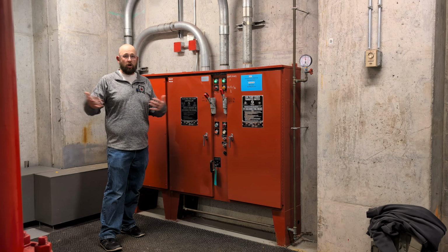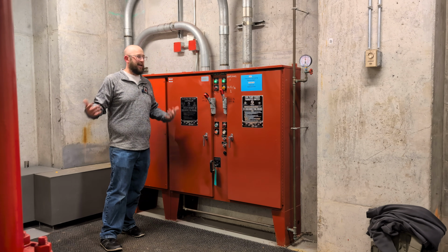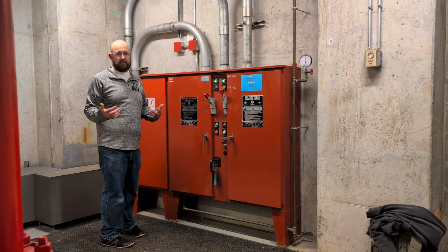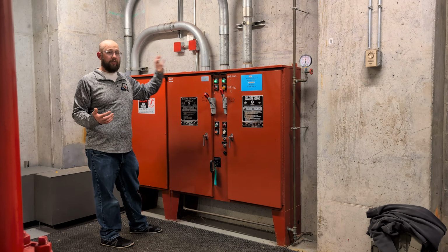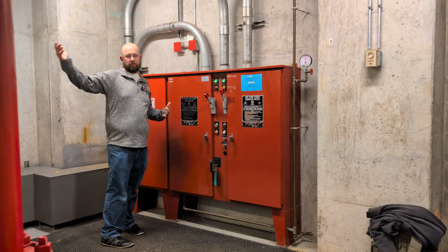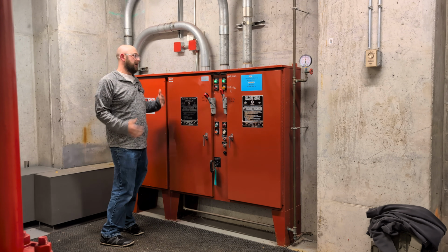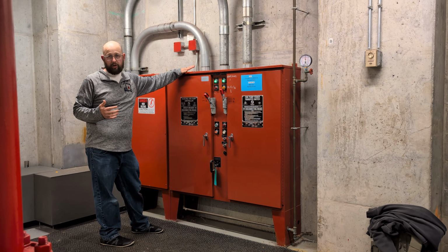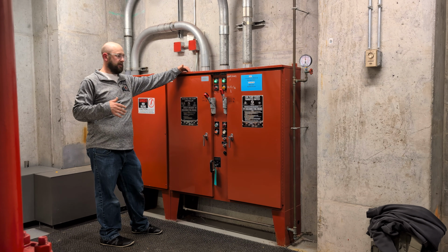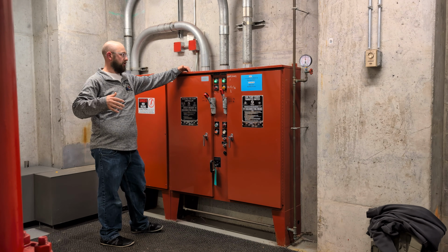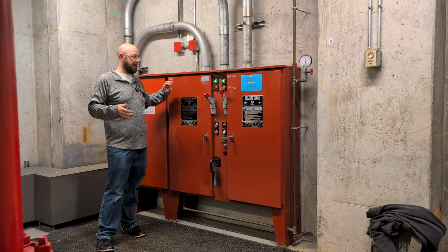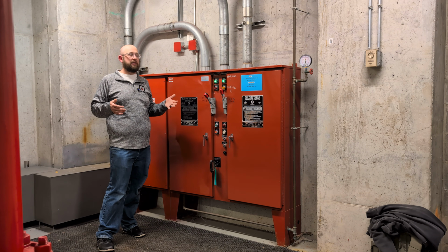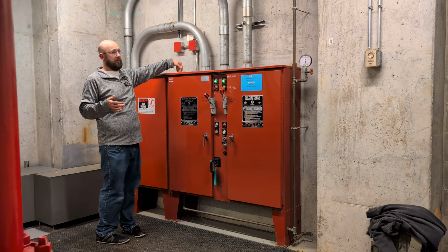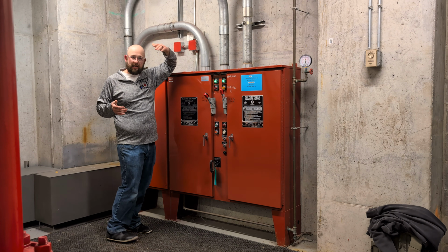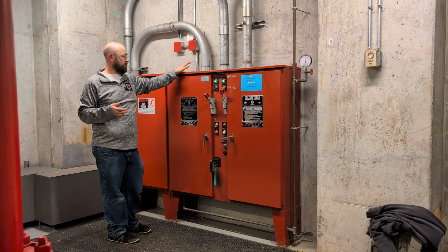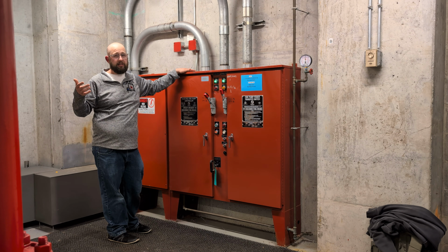So in some cases that could be a guard tower at the building where we have somebody constantly watching that. That typically doesn't happen in many buildings. So usually the way that's done is to actually monitor with the fire alarm system and then send all of our signals to a supervising station where that is constantly attended. And the way we monitor the fire pump is, the fire pump controller is looking at all of those conditions, whether it's the fire pump running or loss of phase or phase reversal, and then it has dry contacts inside that we can monitor with the fire alarm system itself. In this case here, we've got our circuits coming in monitoring that system. And then if we have an issue, we're going to get a supervisory signal at the fire alarm system itself. So that's the way that we're monitoring those and sending it to that constantly attended location.